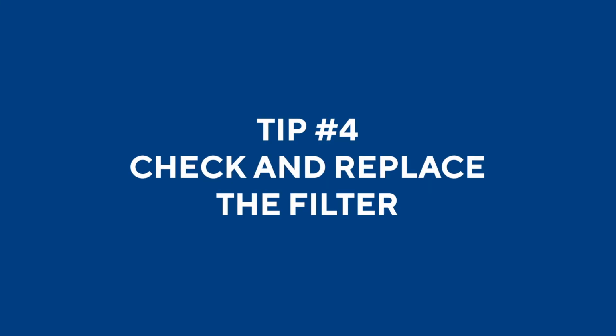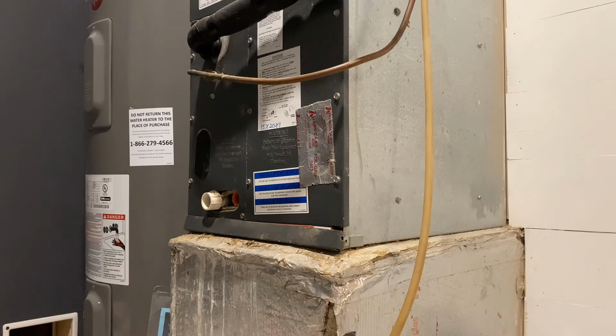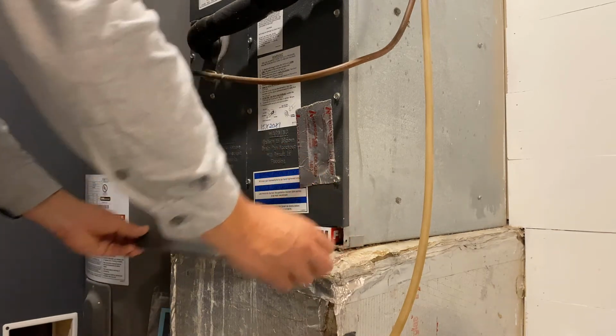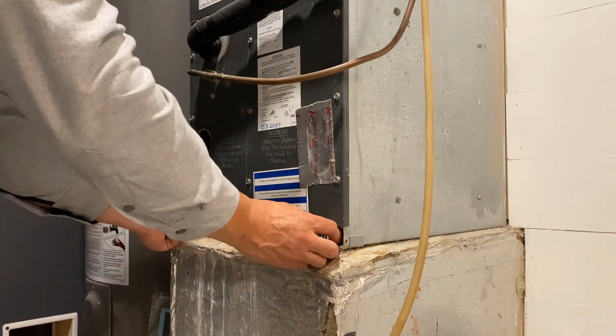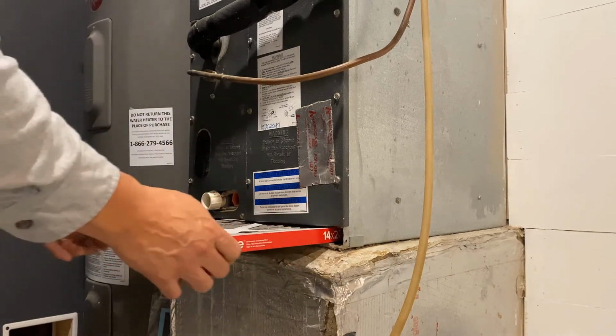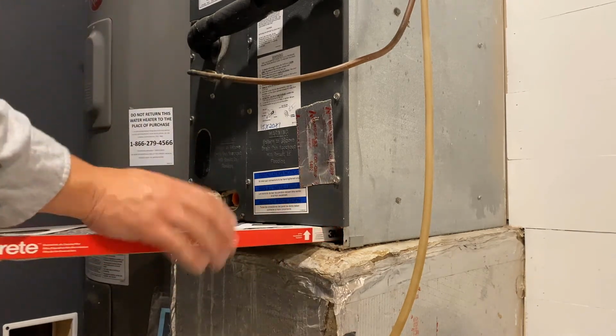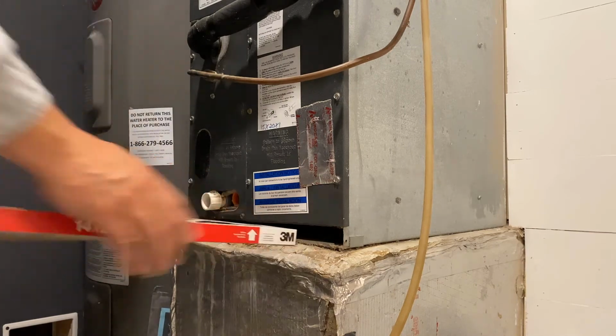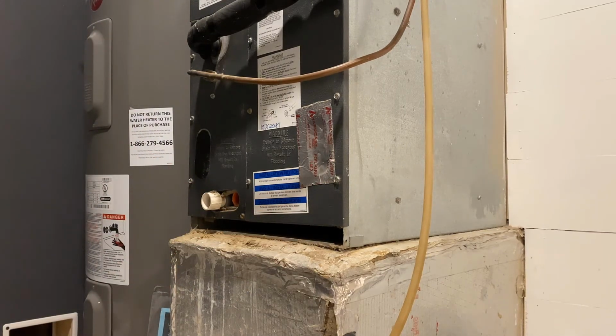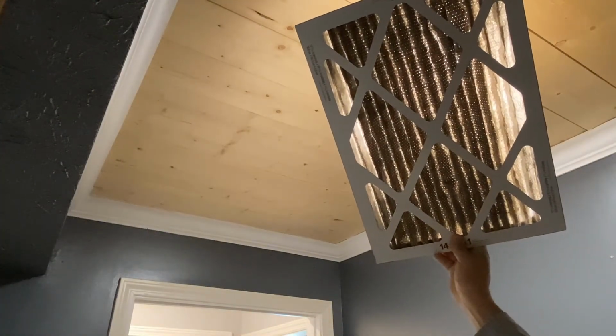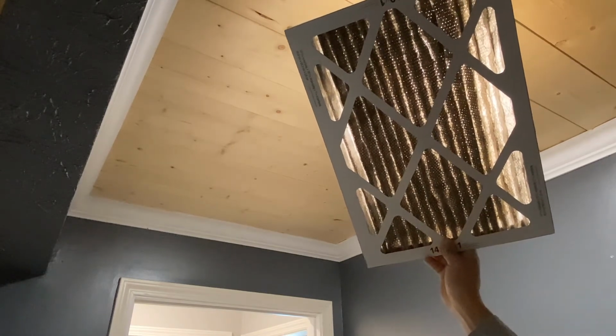Tip number 4. Checking and replacing your filter. If your HVAC unit doesn't seem to be blowing sufficient air through the vents, it could be the result of a clogged filter. Locate your air filter. For this example, the filter is located at the indoor unit. Remove the protective guard and slide the filter out. Filters should be replaced every 30 to 60 days. If you're not sure whether to replace your filter, put it up to the light. If you can see through it, then it's still okay to use.